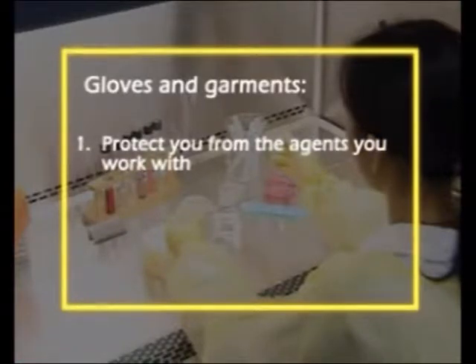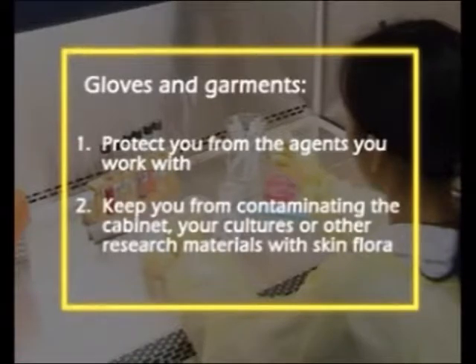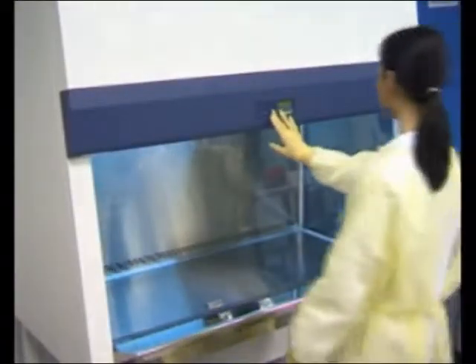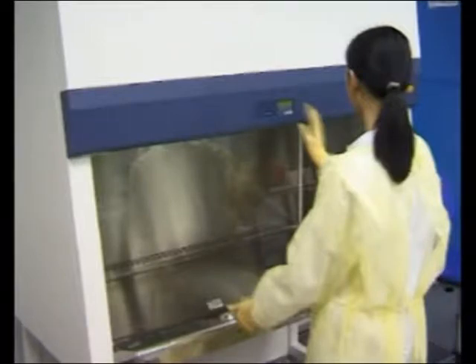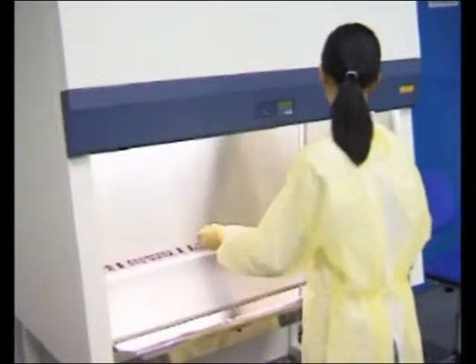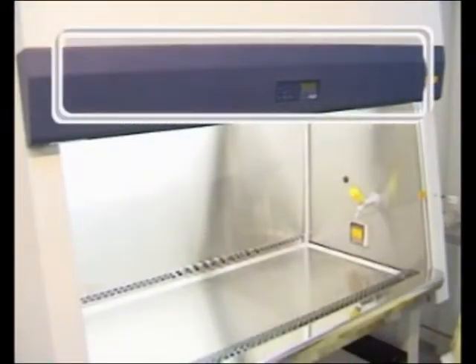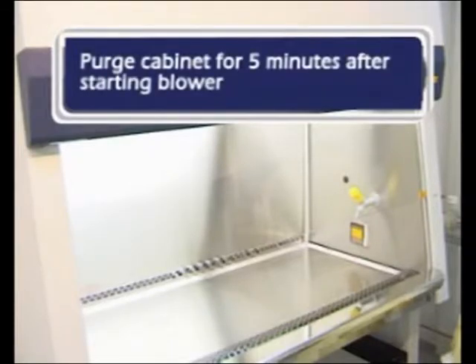Gloves and garments will protect you from the agents you work with and will also keep you from contaminating the cabinet work zone, your cultures, and other research materials with skin flora. If a germicidal UV lamp is being used, you must deactivate the lamp as soon as you enter the laboratory. Raise the front sliding sash to the opening height and turn on the fluorescent lights. Ensure that air intake and exhaust areas of the cabinet are free of obstructions. Start the cabinet blower and allow the cabinet to purge for 3 to 5 minutes. This will remove the airborne contaminants from the work zone and stabilize the cabinet airflow.